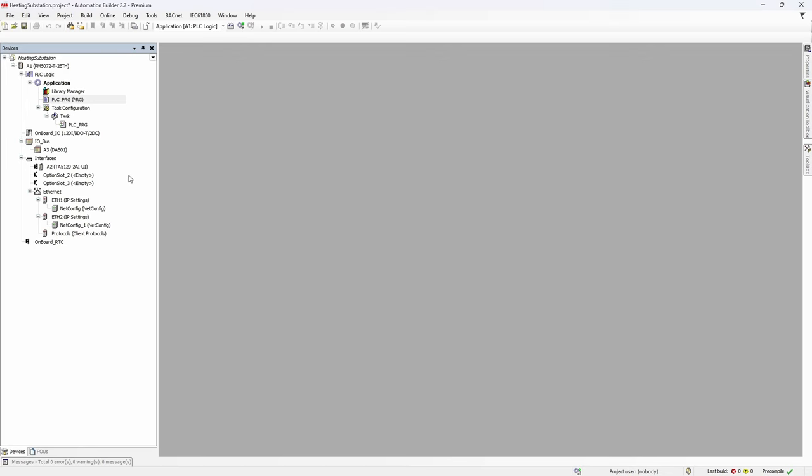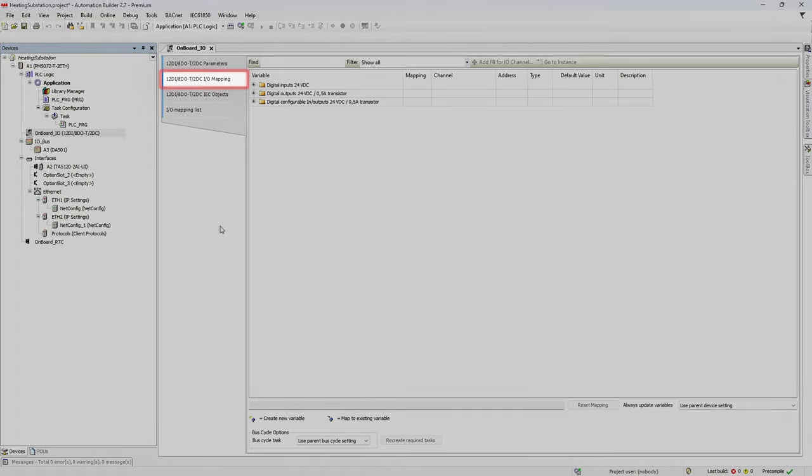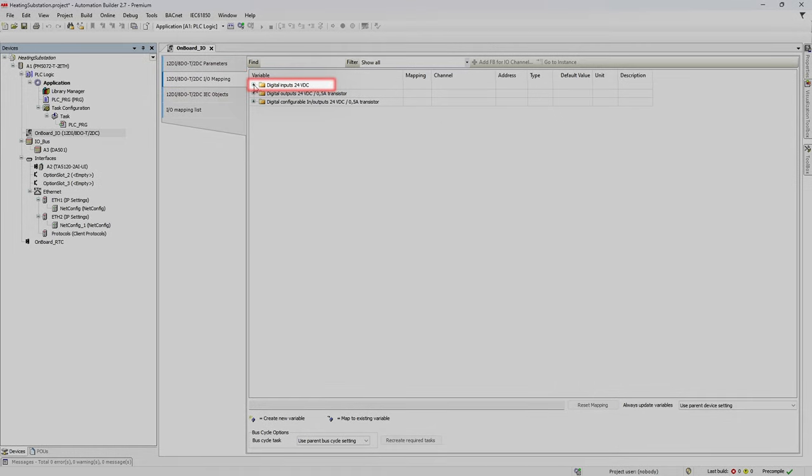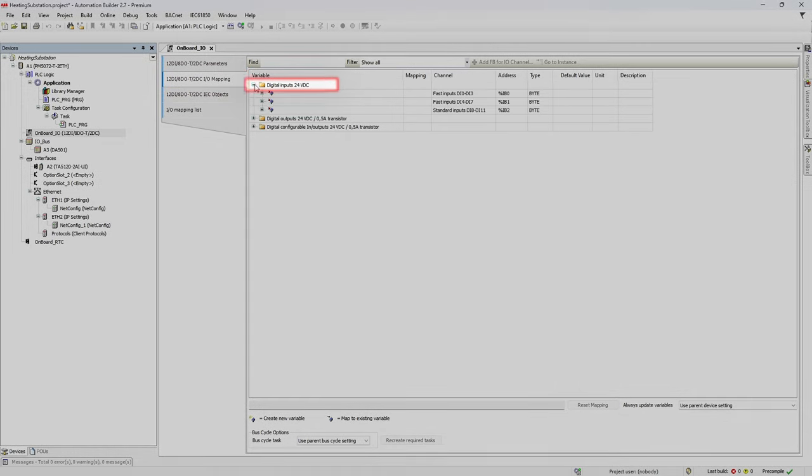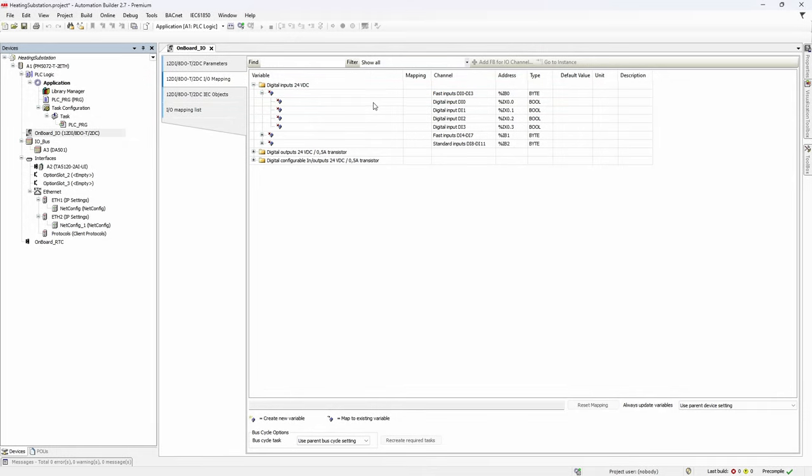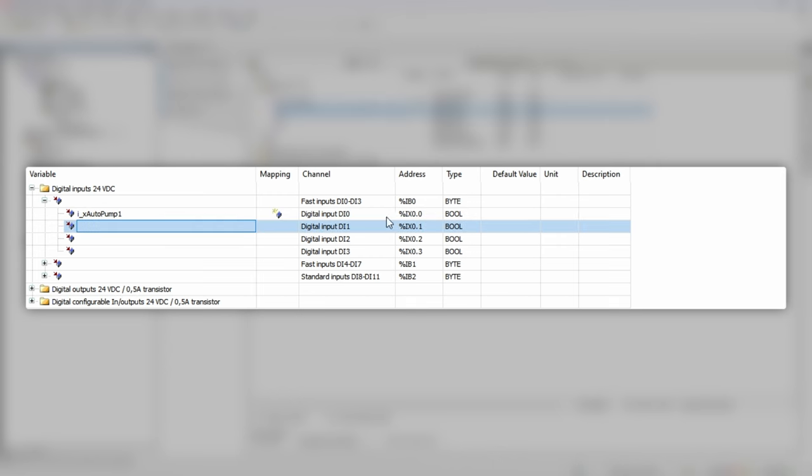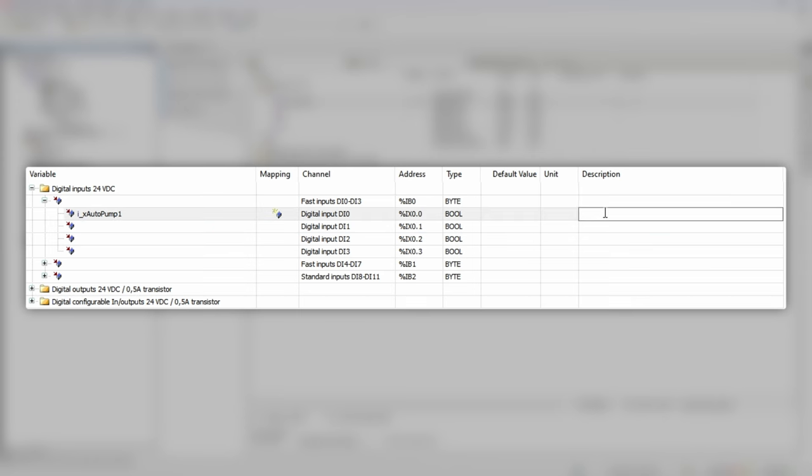There are three ways how you can do it in Automation Builder, and each way may suit better for one or another task. Let's start with PM5072 on-board IO channels. Click to the vertical tab IO mapping, then digital inputs, then inputs di0 di3. Double click variable field of the input di0 and type the name i_x_auto_pump_1. Hit enter and the variable with specific name is created. Description field allows you to elaborate more on how the channel is used.